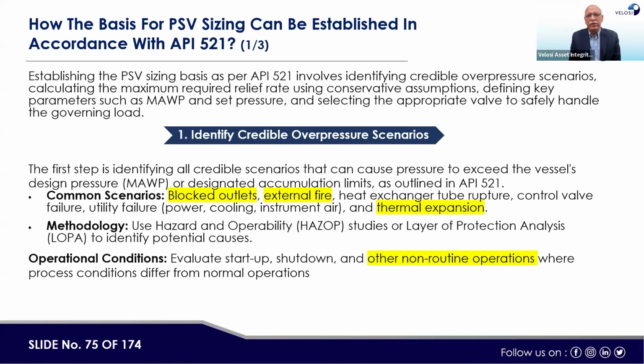Then all these scenarios are also discussed during HAZOP or LOPA analysis, to check whether we have the right protections provided to avoid high pressure in the system. In those scenarios, if high pressure comes, what kind of layer of protection are we providing? Whether it would be an ESD system, and along with the ESD system there would also be a PSV or PRV, or along with the ESD system maybe a BDV system. All these systems are selected based on HAZOP and as per API 521 guidelines.